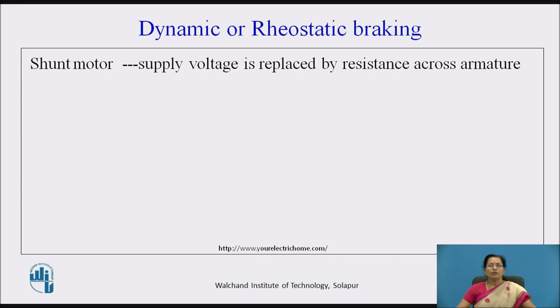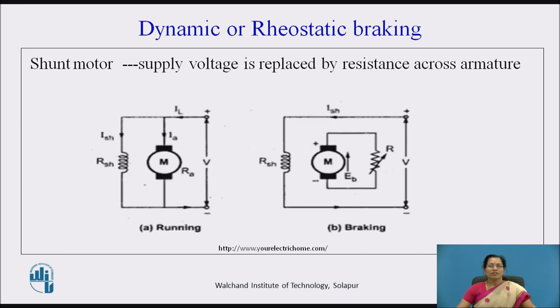For a shunt motor, the supply voltage is replaced by a resistance across the armature for dynamic or rheostatic braking. The armature current direction is downward and the motor rotates in the clockwise direction. For dynamic braking, this armature supply is disconnected and a variable resistance is connected across the armature. The back EMF across the armature causes the current through the armature to reverse, so the current direction is now upward.